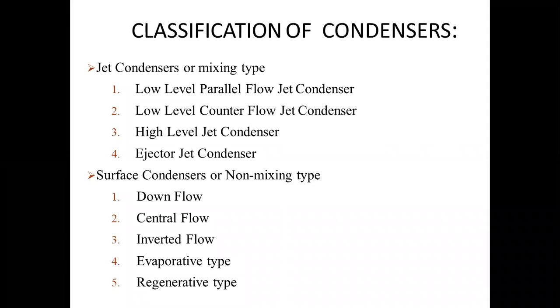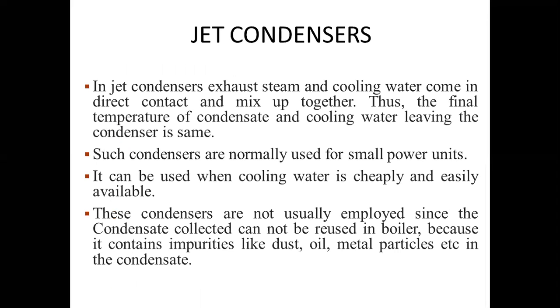If we are talking about classification of condensers, there are two types of condenser. One is the jet condenser, the other is the surface condenser. Jet condensers can be low level parallel flow, low level counter flow, high level jet condenser, and ejector jet condenser. While in the case of surface condensers, it can be downflow, central flow, inverted flow, evaporative type, and regenerative type. Let us discuss the jet condenser. In a jet condenser, exhaust steam and cooling water come in direct contact and mix together.